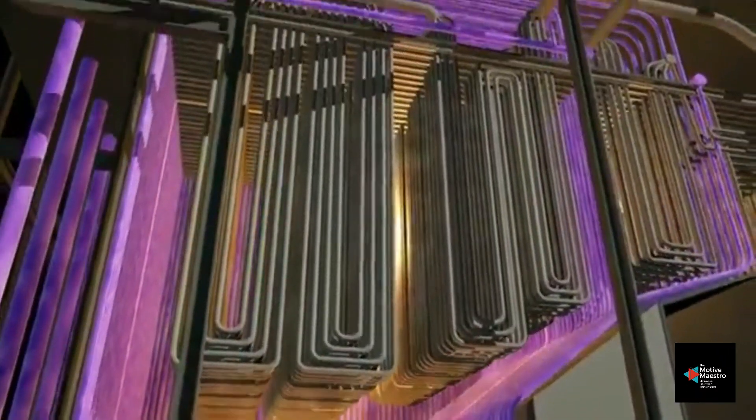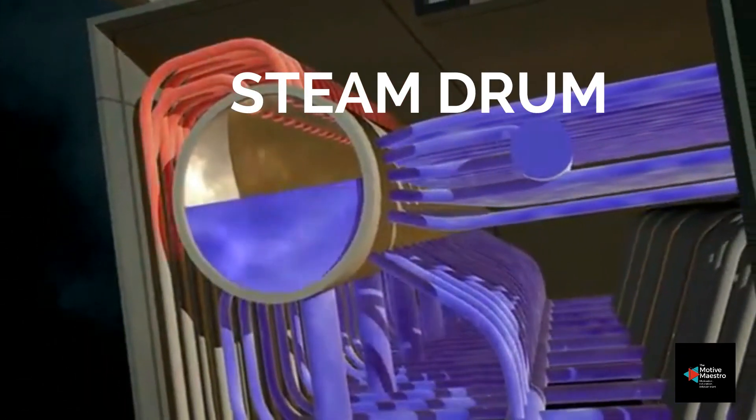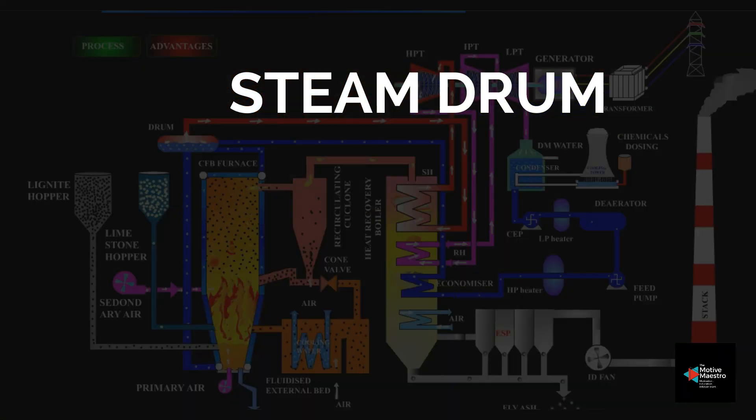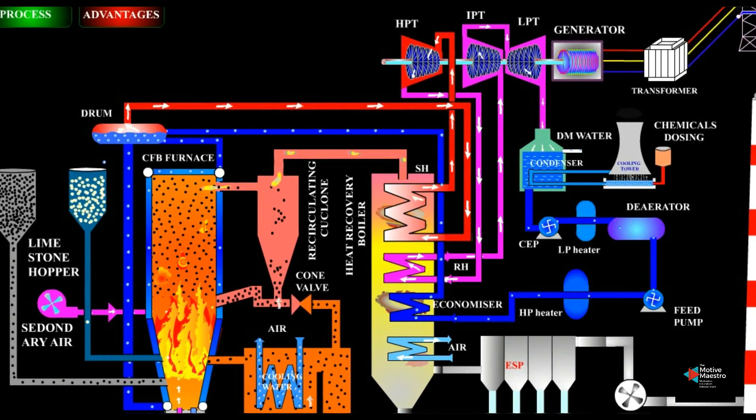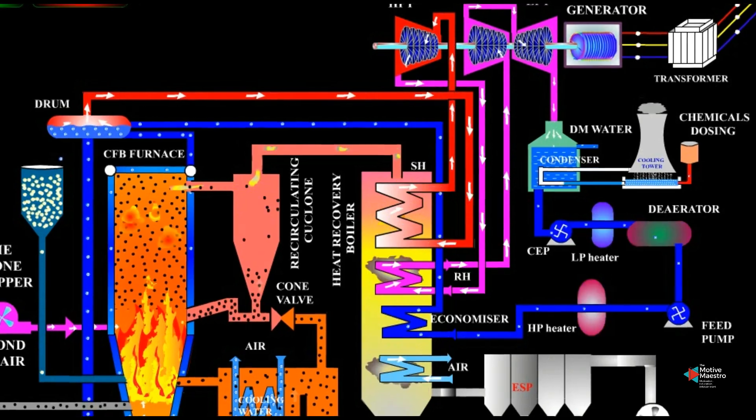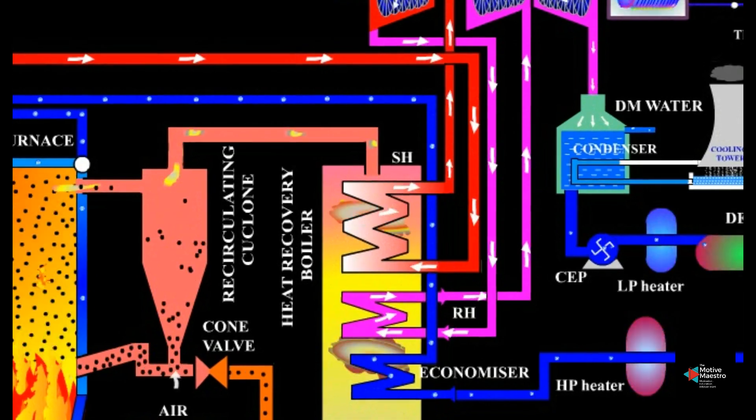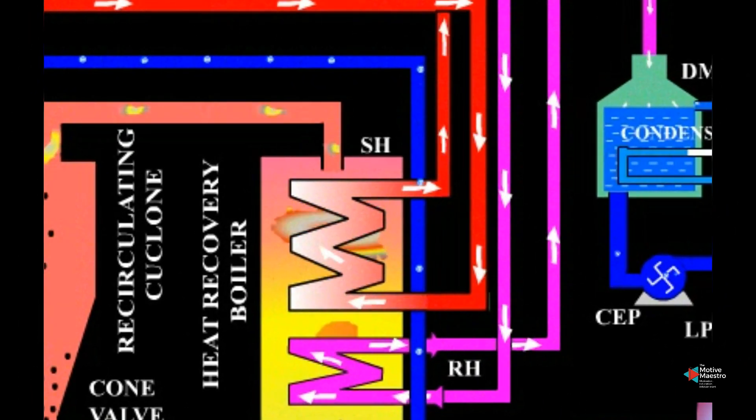We'll then send the water around to the furnace. Our water is going to change to steam. It's not going to be completely dry yet, there's going to be particles of moisture in the steam. That is what we see normally when we think about steam. In the steam drum we'll begin to separate that moisture from the steam, sometimes using steam separators or steam cyclones, sometimes using arrangement of baffles or a combination of both. We'll then send our steam to a super heater where we will really heat that steam up.